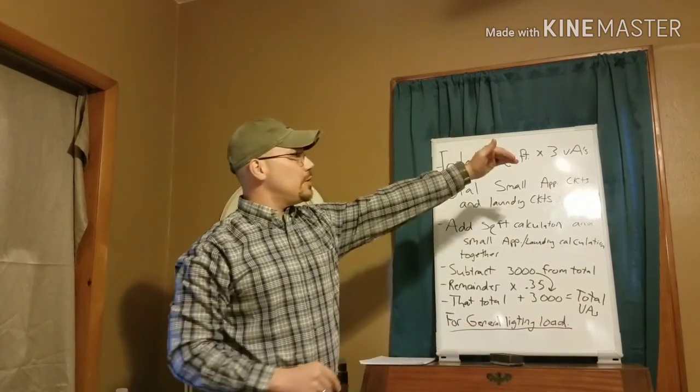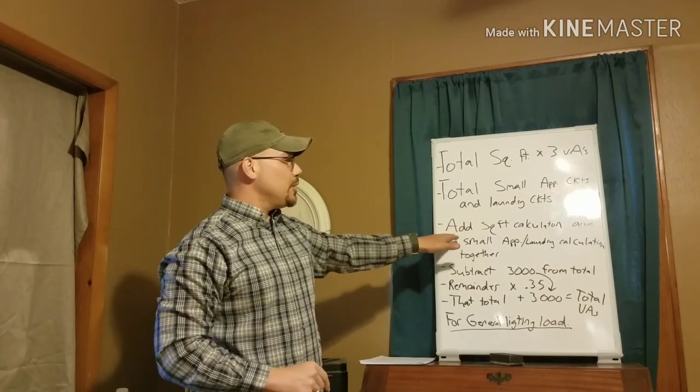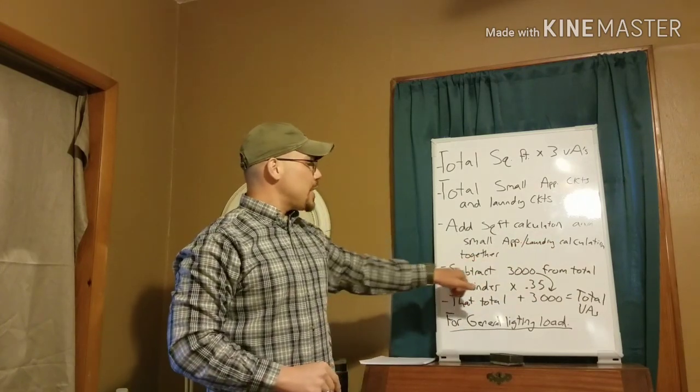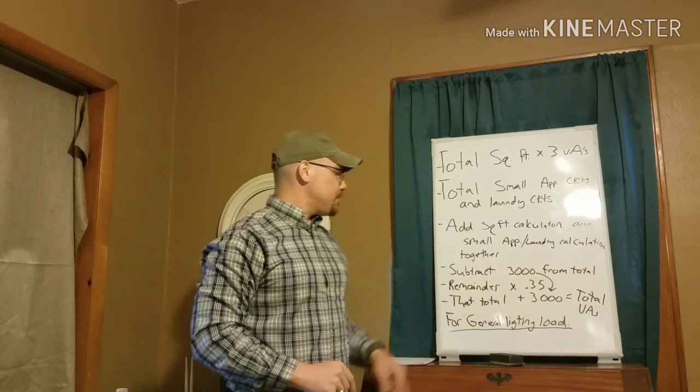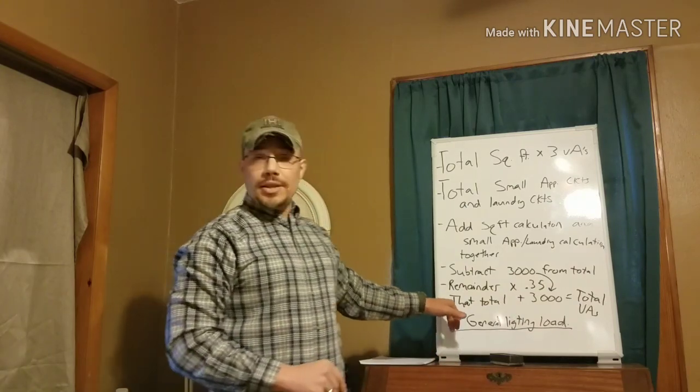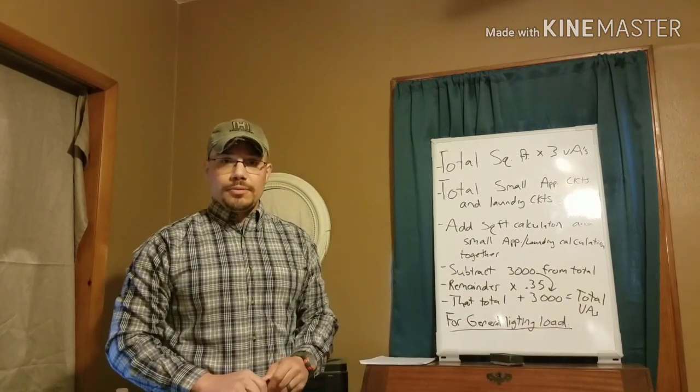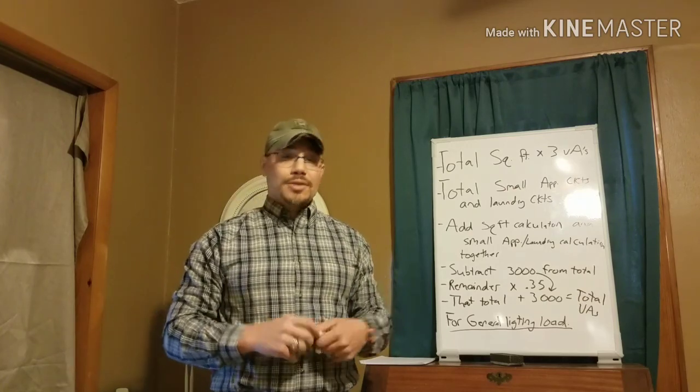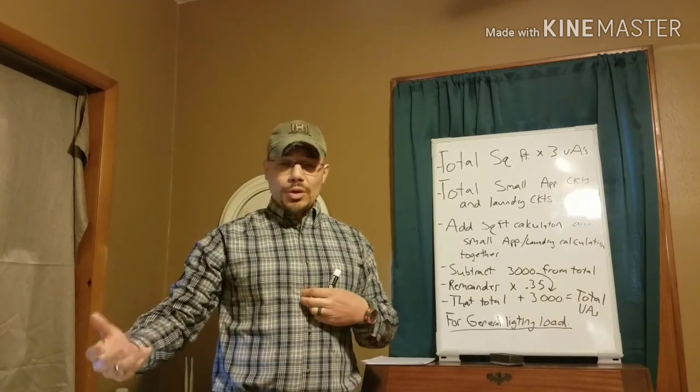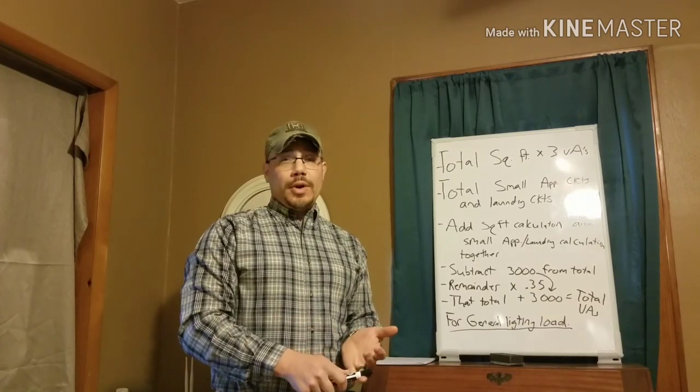So we take our total square feet and run through it again. Total square feet times 3 VAs per square foot. So there's the way to think about it: total square feet times 3 VAs, total small appliance circuits and laundry circuits times 1,500 VAs. You're going to add your square feet calculation and your small appliance laundry circuit calculation together. Subtract 3,000 from that total. The remainder after that 3,000 is gone times 0.35. Then you take that total plus your 3,000 back in for your total VAs for your general lighting load. I hope this made sense. Like I said, this is just a general lighting load portion of the load calculations. The next video I'm going to talk about is going to be our dryer and then also our range calculations.